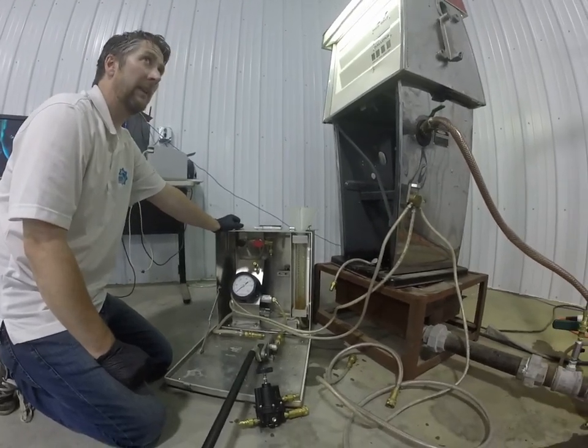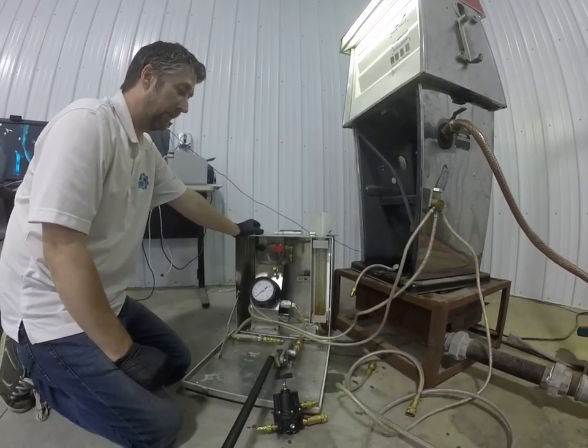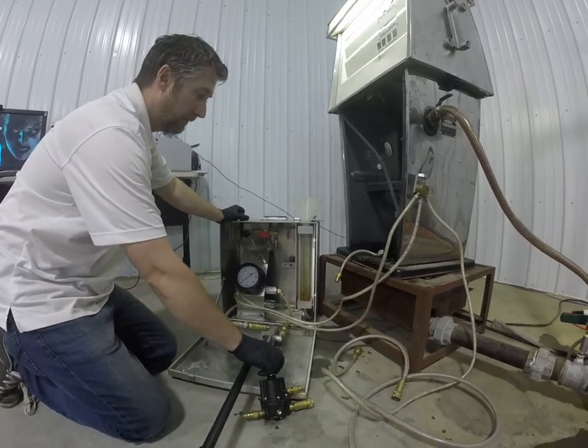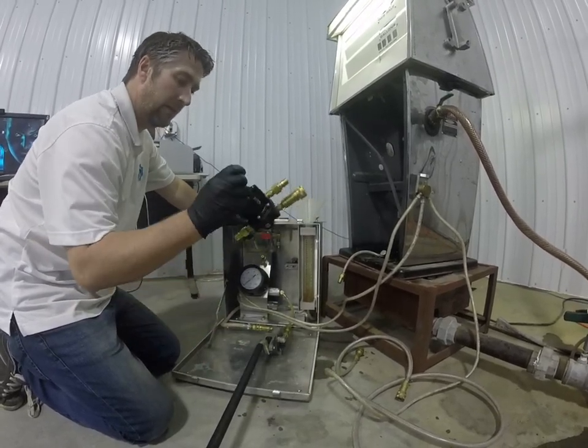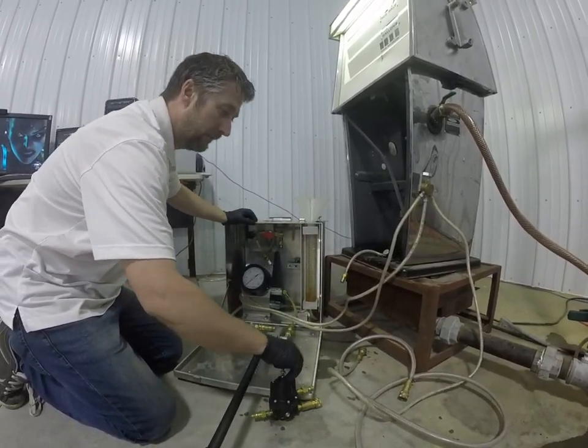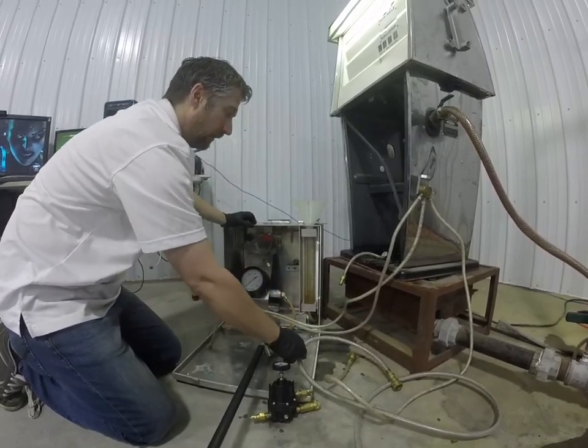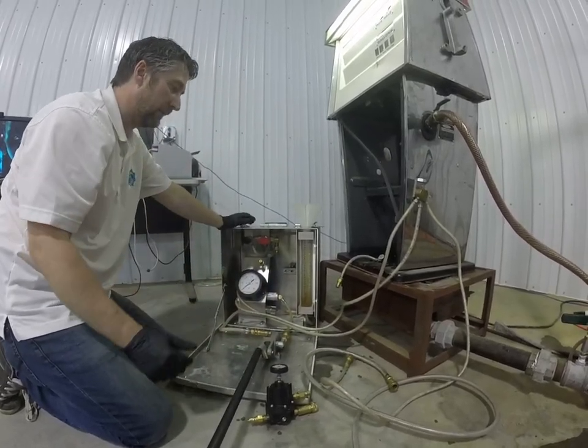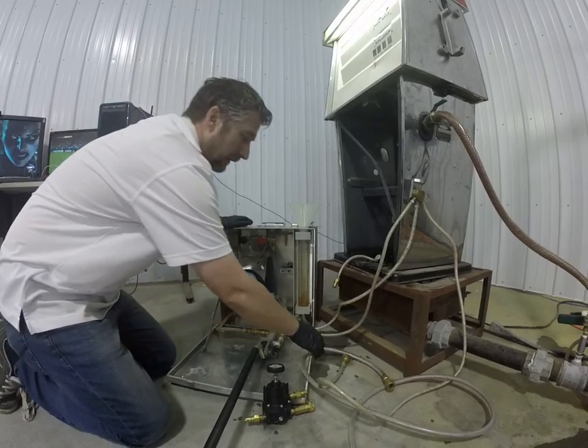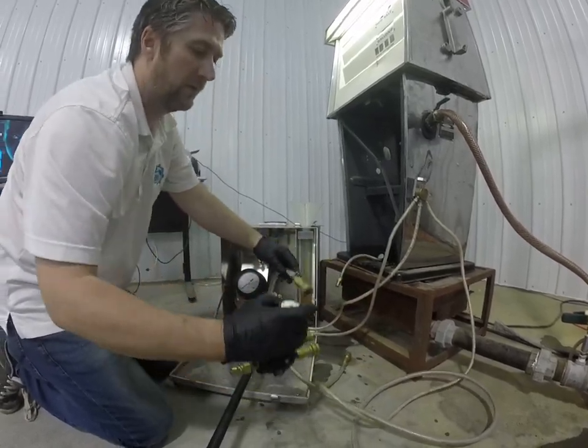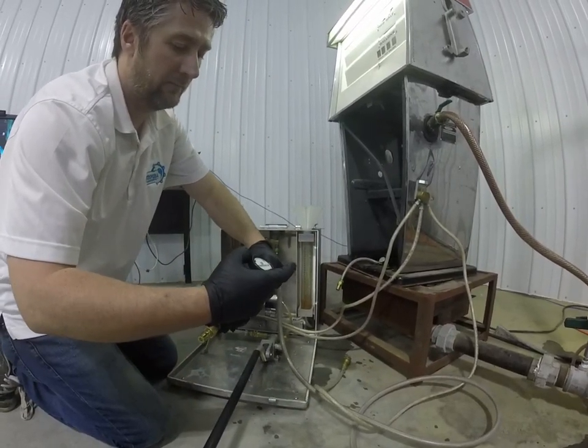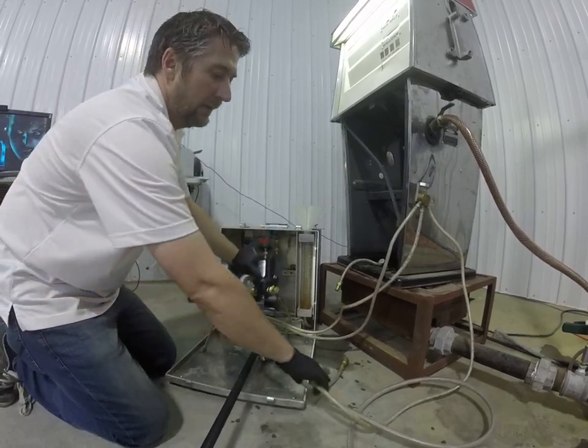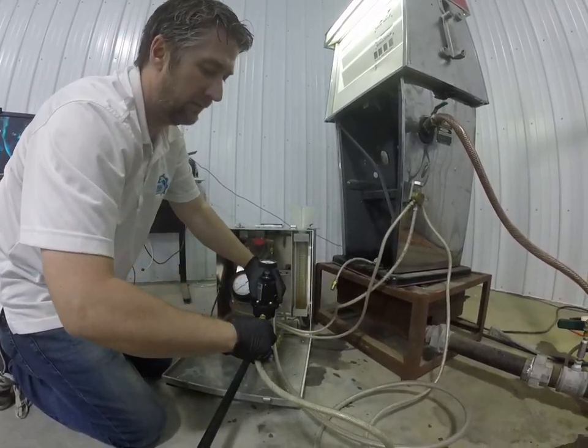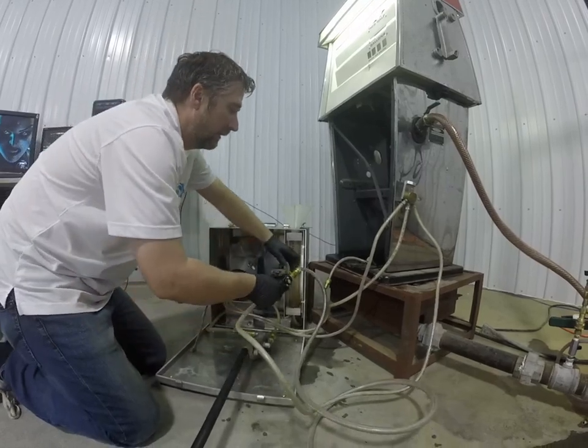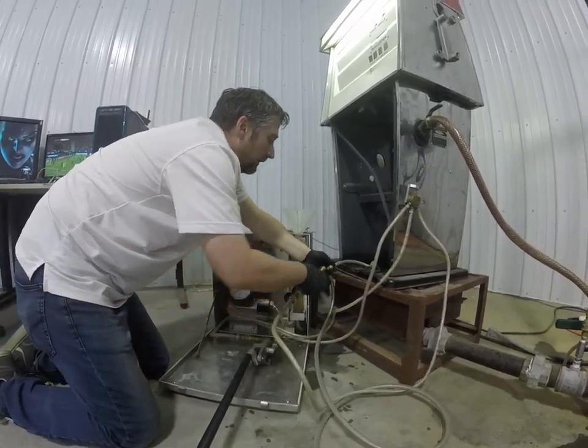Okay, in order to test the functionality of a leak detector, you're going to need a few things. You're going to need the Petro-Tite line tester, the pressure reducing regulator, and then the supply drain hose that comes with it. The first step in testing is we're going to connect the drain hose to the regulator. Then we can connect the line tester to the regulator, and then the regulator to the pigtail.